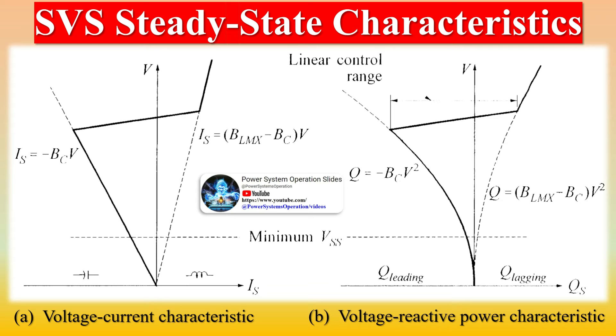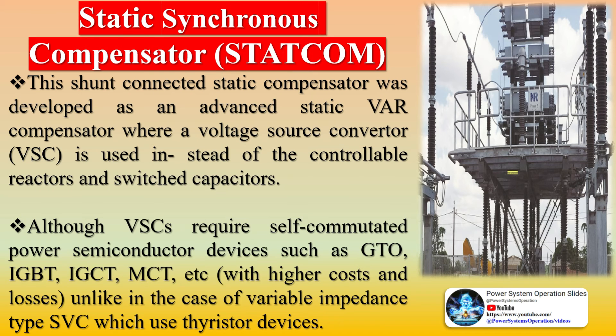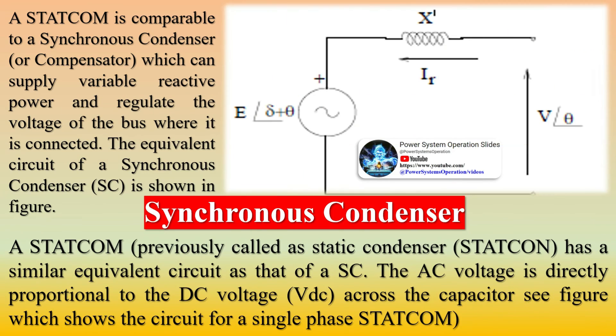In an SVC, the maximum reactive current is determined by the rating of the passive components — reactors and capacitors. STATCOM is a device for regulating poor power factor and poor voltage, based on a power electronics voltage source converter, and can act as either a source or sink of reactive AC power. If connected to a source of power, it can also provide active AC power. STATCOM provides better damping characteristics than the SVC as it is able to transiently exchange active power with the system.